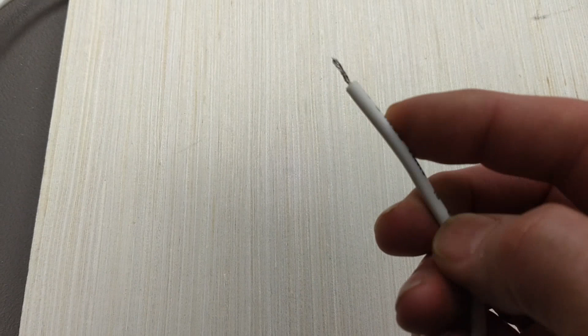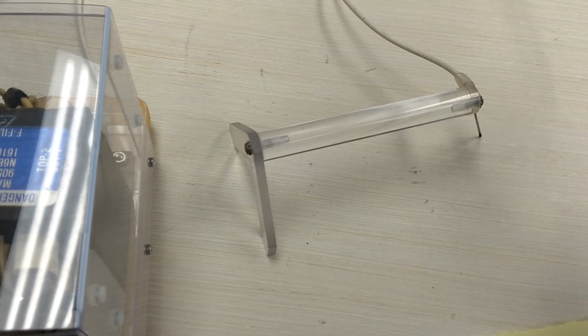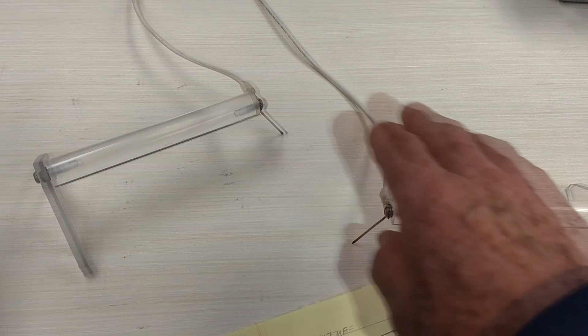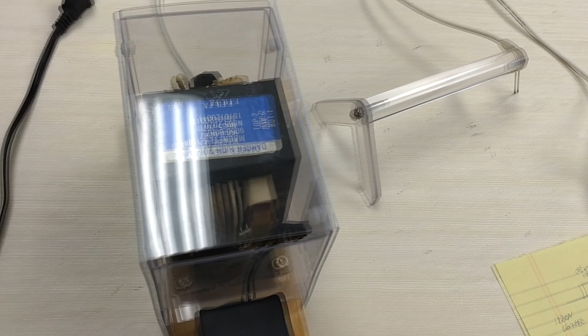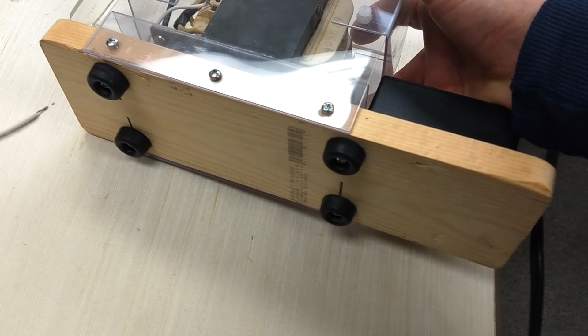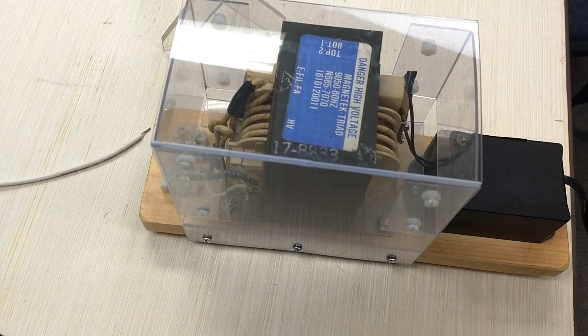You might be tempted to want to ground that transformer—don't do that, because then there's a danger of having a path to ground from the other probe. The way it is now, neither probe has a path to ground. I also wanted to point out this piece of wood is up on rubber feet, just in case we spill water while painting the soda solution on the wood. I want to make sure that wood does not get wet.